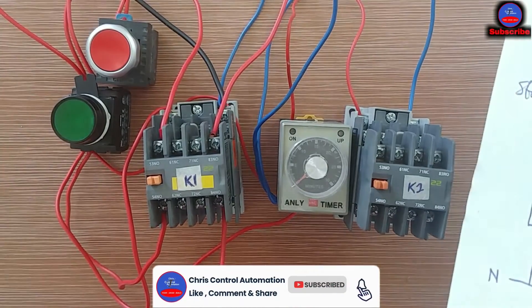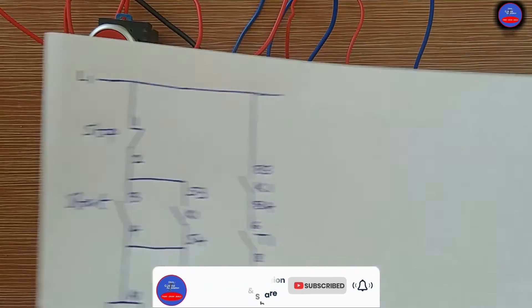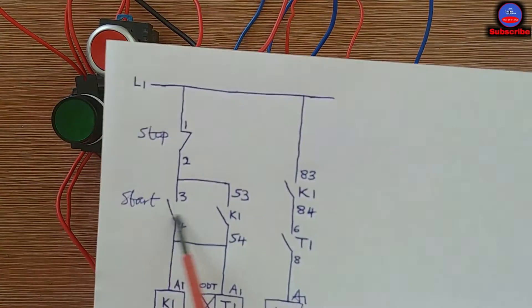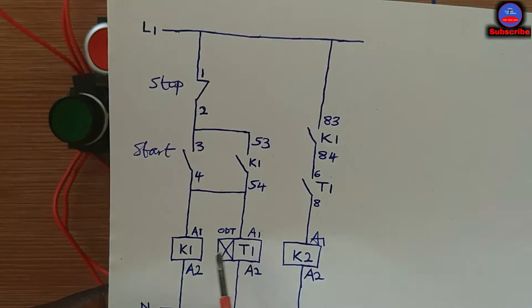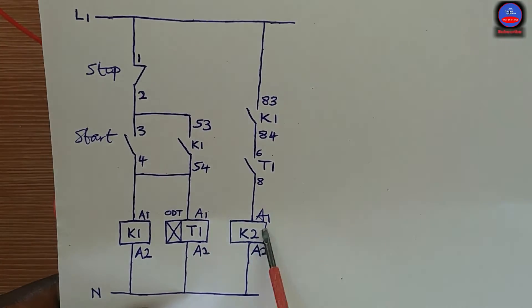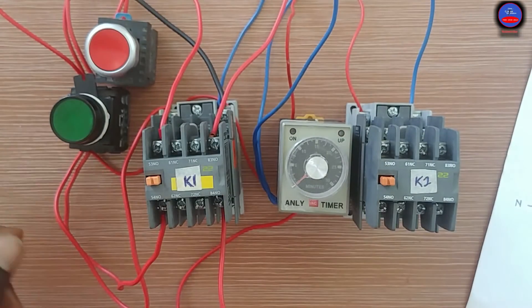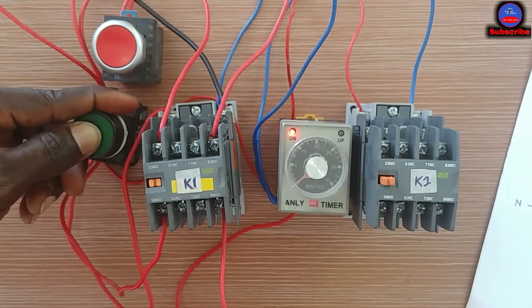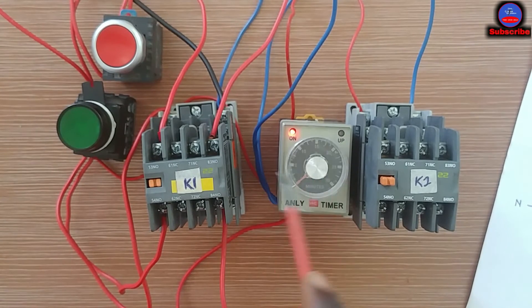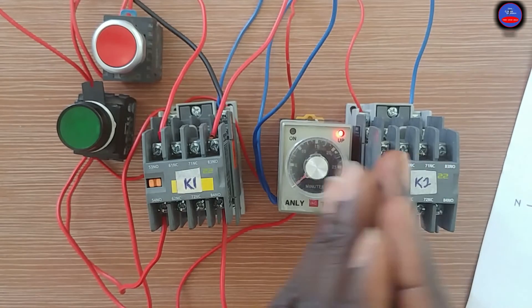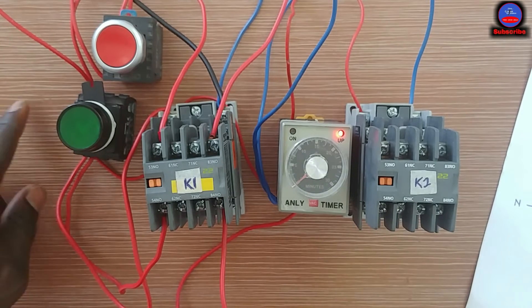Alright engineers, this is the complete wiring. Let me explain the operation once again: when I press the start push button, K1 and the timer both energize, the timer counts, and after the preset time K2 energizes. Let's demonstrate — I'm pressing the start push button now. You can see K1 and the timer are energized. After the preset time, Contactor 2 comes on — you see that! They started in sequence.